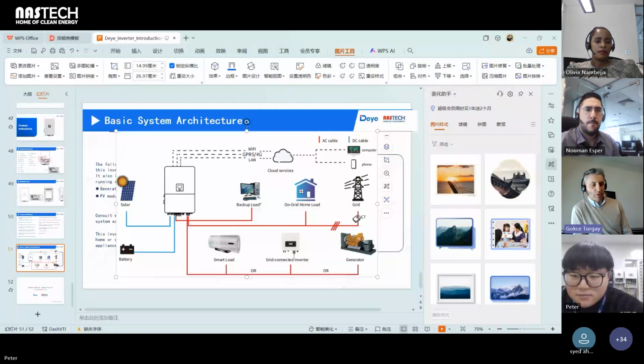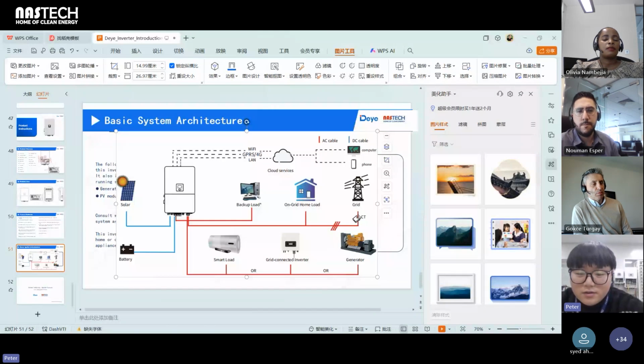Can they use the string inverter as the smart load port on the battery side and then connect the 15 kilo? You mean connect the string inverter to the hybrid inverter generator port? Yeah. If you already have a hybrid inverter with a battery, then you can connect a PV inverter, a string inverter, to the hybrid inverter on the generator port so that the system can work together. Any issue with the string side being like 4 times the capacity of the hybrid inverter? Do we need any zero export kind of functionality to limit the string inverter's output into the hybrid inverter in this scenario?